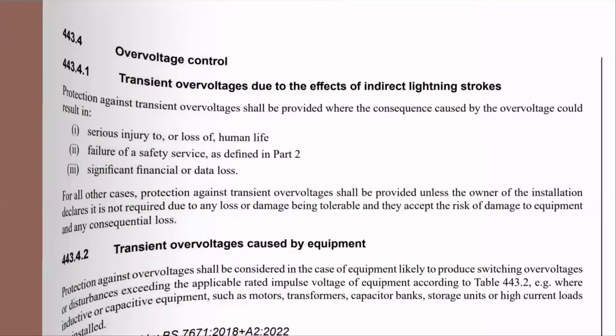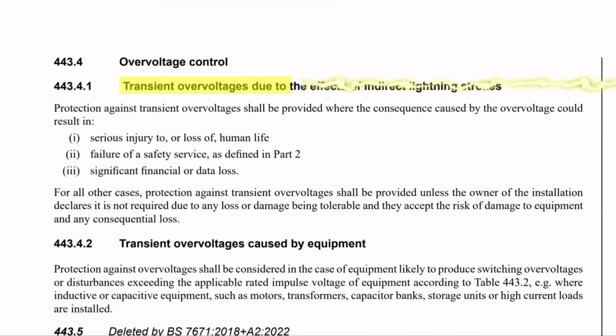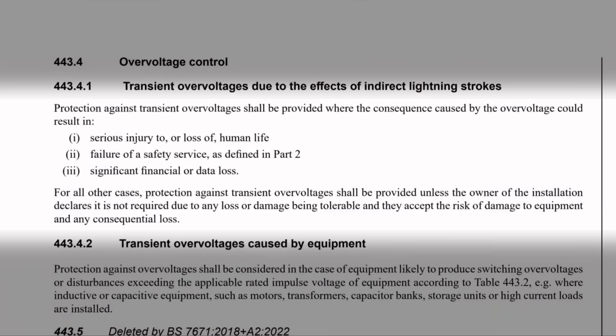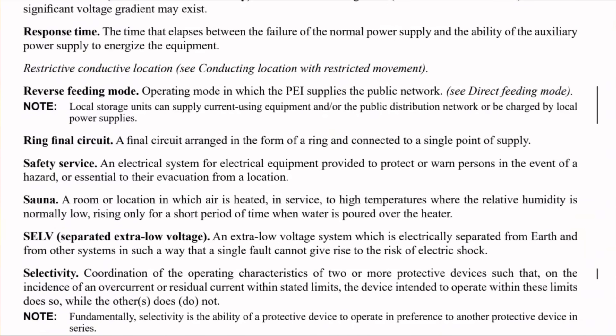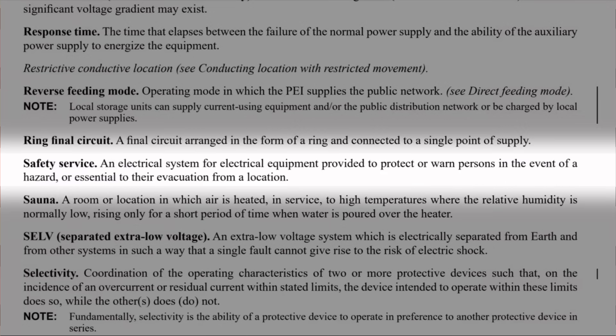In regulation 443.4.1, which relates to transient overvoltages due to the effect of indirect lightning strokes, we read: protection against transient overvoltages shall be provided where the consequences caused by the overvoltage could result in: one, serious injury to or loss of human life - can't argue with that one; or two, failure of a safety service, as defined in part two, bearing in mind that this definition tells us that this is an electrical system provided to protect or warn persons in the event of a hazard or essential to their evacuation from a location.